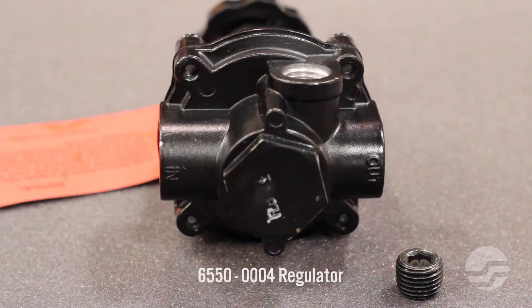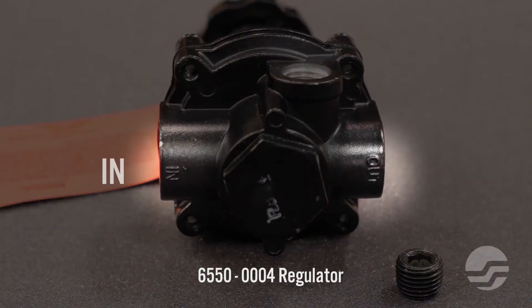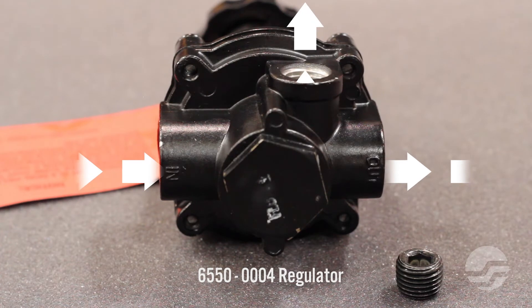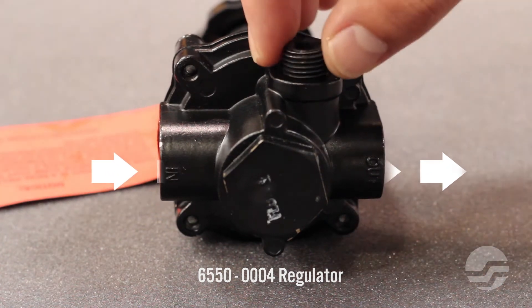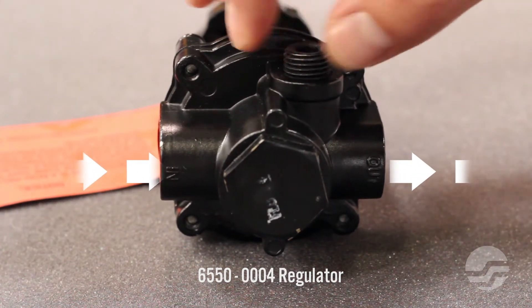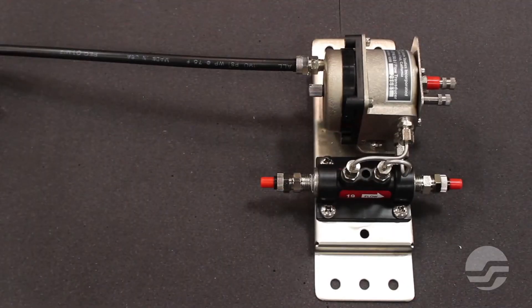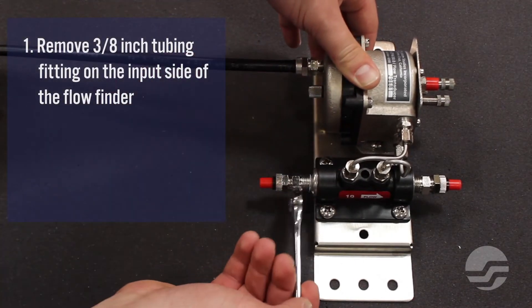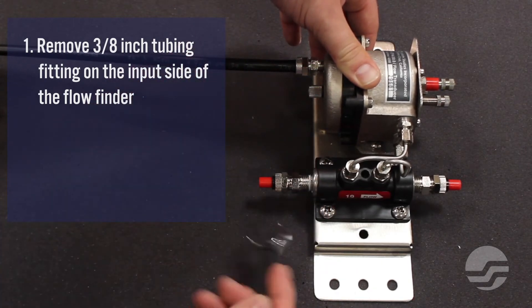In this installation, we are dry-fitting components together. Please use thread-seal tape at all threaded connections. The regulator is marked on the bottom to designate the input and output sides. We will be using only one output from the regulator. Use an Allen wrench and the included plug to seal the second outflow. Mounting a regulator to the flow measurement assembly involves removing the 3/8 inch tubing fitting on the input side of the flow finder.